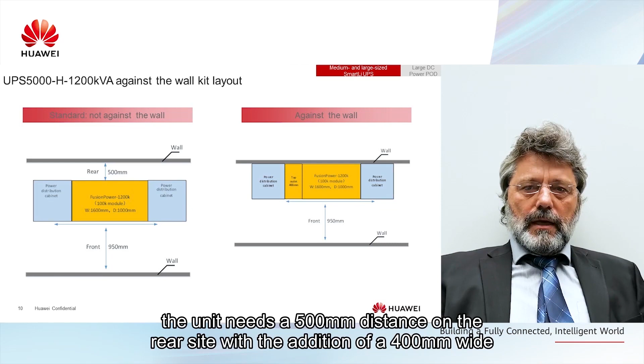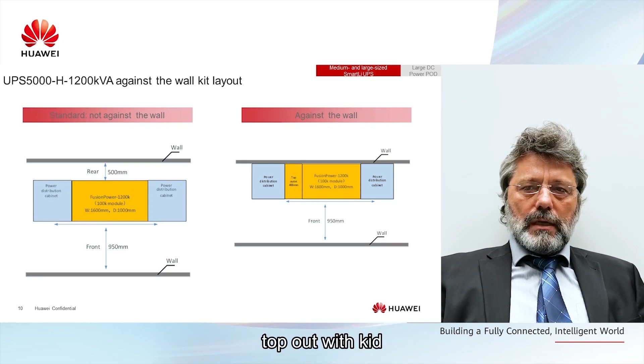Here we can see the top view arrangement of the accessory kit to put the UPS against the wall. In the standard layout, the unit needs a 500 mm distance on the rear side. With the addition of a 400 mm wide top outlet kit, the system redirects the hot air to the top side of the UPS. In front, a 950 mm service space is recommended.